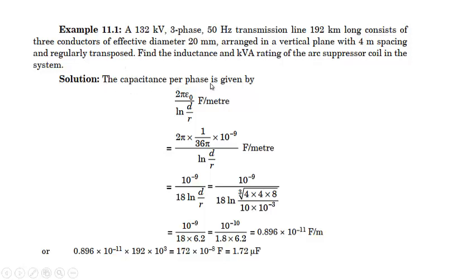The capacitance of the phase is given by, as we know, 2 pi epsilon divided by ln of d by r, where d is d equivalent. Since they are in the vertical plane, d equivalent will be equal to cube root of 4 into 4 into 8, and its radius is 10 mm, that is 10 into 10 to the minus 3. Calculating this and multiplying by the total length of the line, it will be equal to 1.72 microfarad.